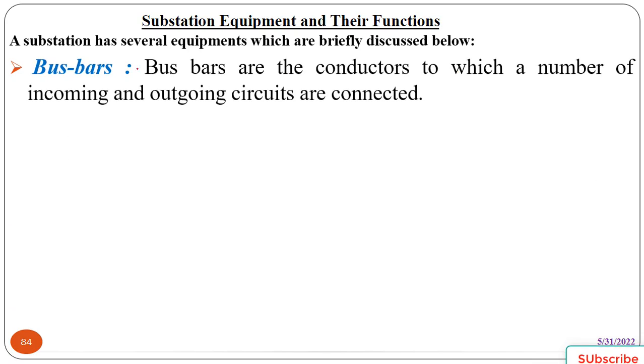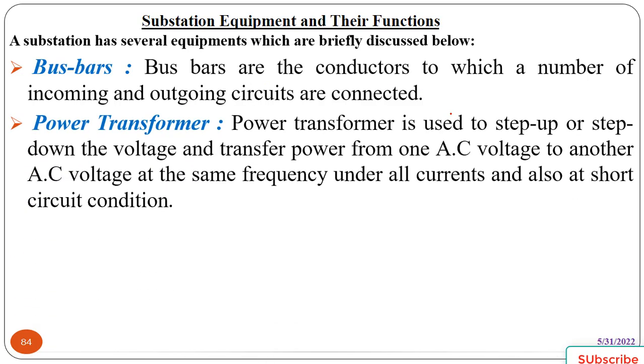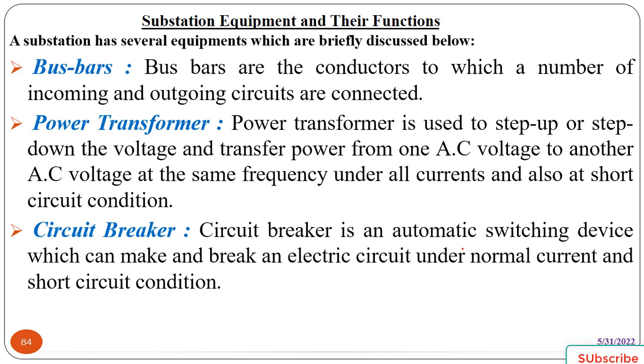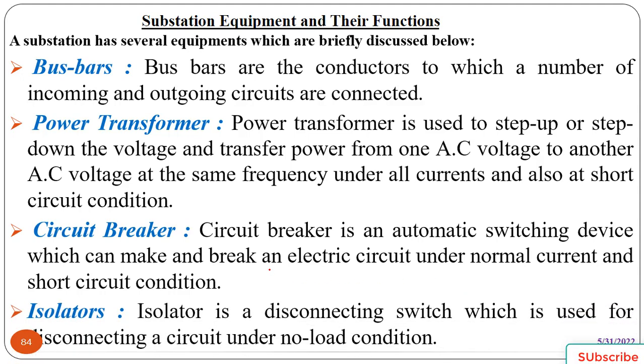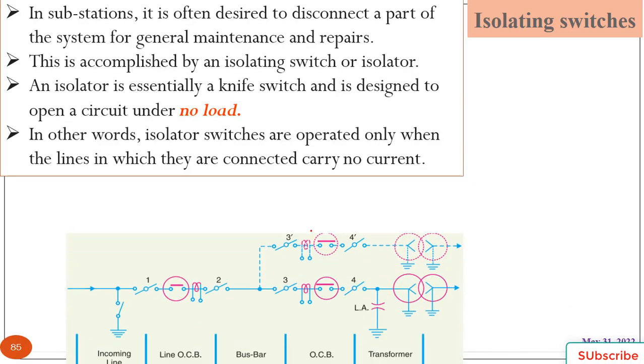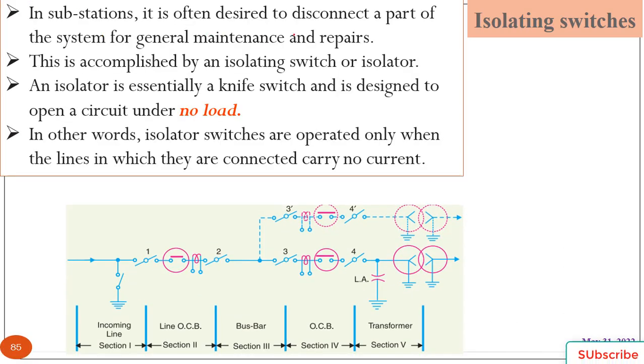So, substation equipment and their functions. The substation has several pieces of equipment, which are briefly discussed. Bus bars are the conductors to which a number of incoming and outgoing lines are connected. A power transformer is used to step up or step down the voltage. A circuit breaker is an automatic switching device which can make or break an electric circuit under normal and short circuit conditions. An isolator is a disconnecting switch which is used for disconnecting a circuit under no load conditions. In a substation, it is often desired to disconnect a part of the system for general maintenance and repair. This is accomplished by isolating switches or isolators.